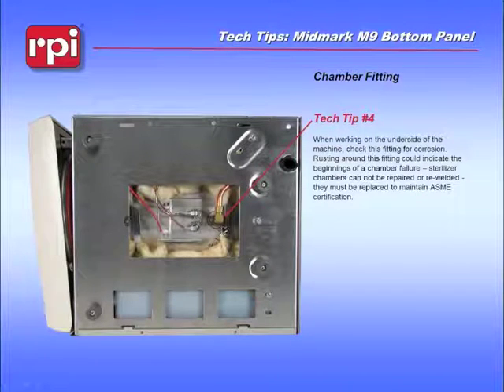Now, if you start to see problems with this joint that is welded in place, this is a non-repairable problem. We do not recommend doing any repairs to a sterilizer chamber. You cannot weld them. You need to be ASME certified to do that kind of work. It is not advised. Once these seals fail, this one around here, the chamber needs to be replaced. Please don't try to have them repaired.